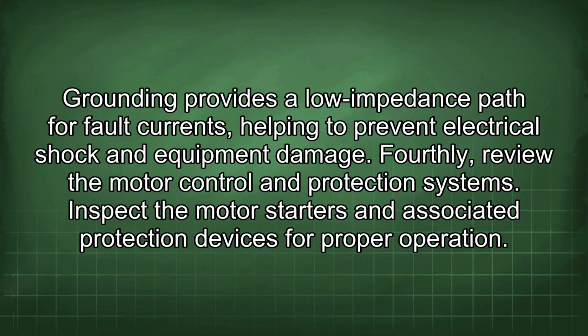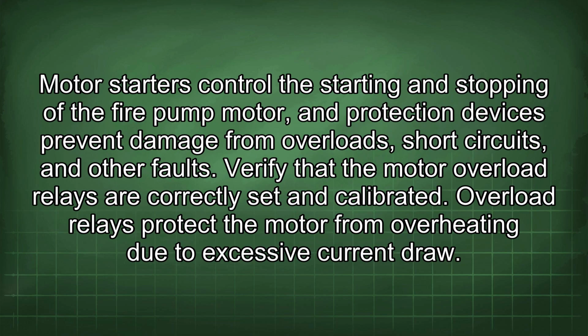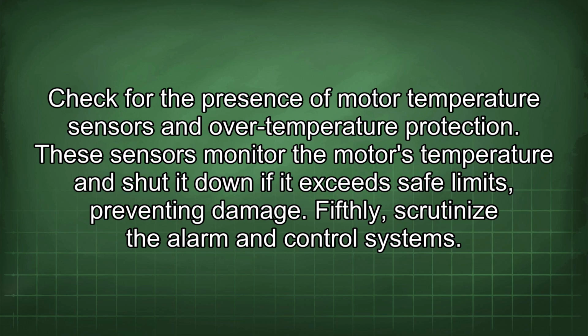Fourthly, review the motor control and protection systems. Inspect the motor starters and associated protection devices for proper operation. Motor starters control the starting and stopping of the fire pump motor, and protection devices prevent damage from overloads, short circuits, and other faults. Verify that the motor overload relays are correctly set and calibrated. Overload relays protect the motor from overheating due to excessive current draw. Check for the presence of motor temperature sensors and over-temperature protection. These sensors monitor the motor's temperature and shut it down if it exceeds safe limits, preventing damage.